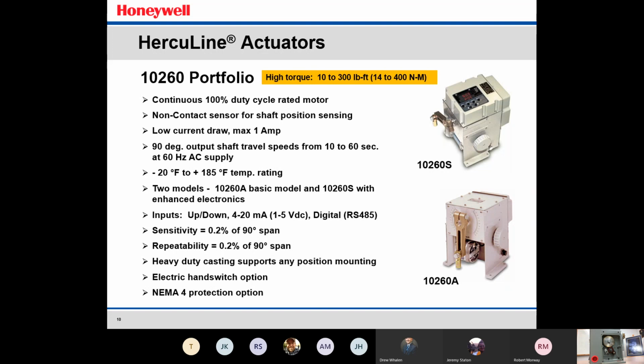The actuator has very low current draw. It has an asynchronous motor that is driving this actuator, and at the end here, I have a 10260 on the bench. We're going to open it up, and I'm going to show you a little bit about the internal workings of the actuator. But the motor on the actuator is actually protected from excess torque by a fiber mesh gear that is a breakaway gear. In the event that you have 2 times the rated torque on the actuator, that fiber gear will break before it damages the other more expensive components on the actuator. And that fiber gear is literally like 15 to 20 bucks. So I'd much rather replace that than a $500 to $1,000 motor on the actuator.